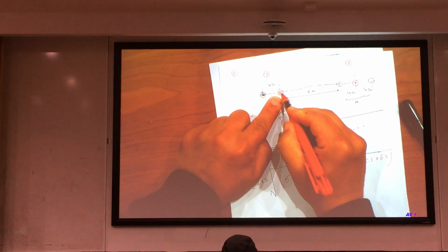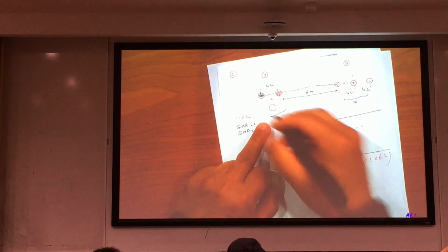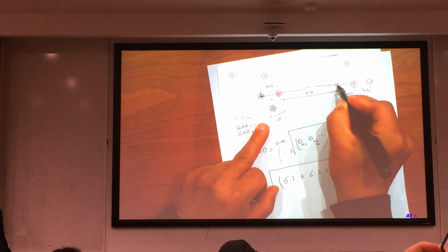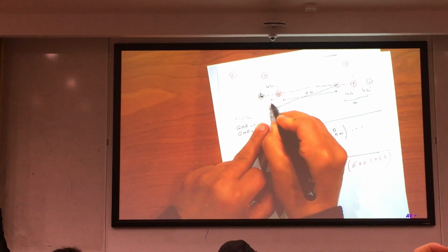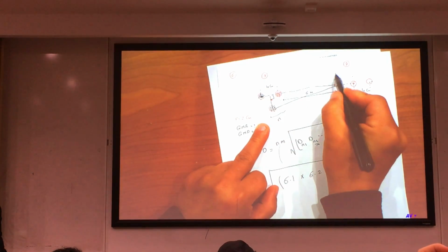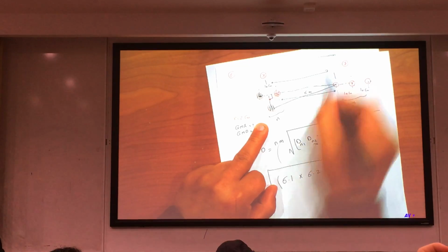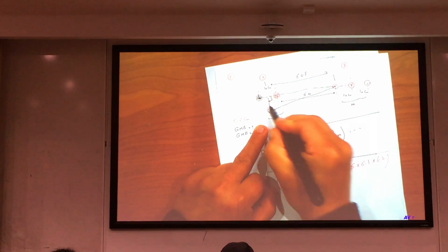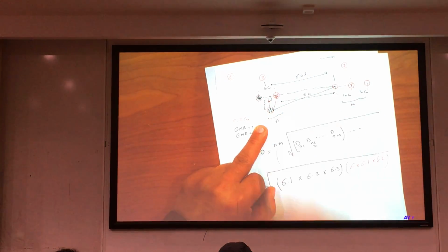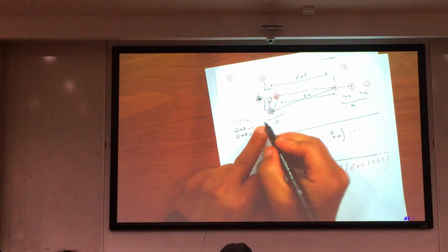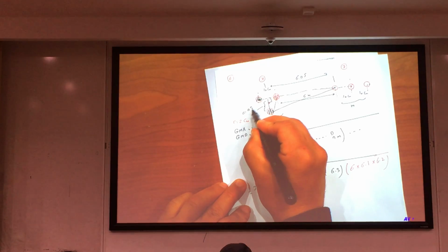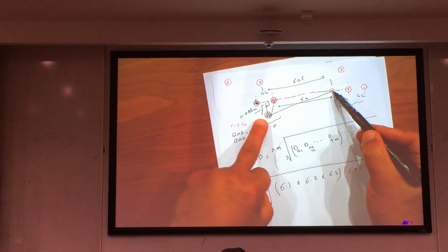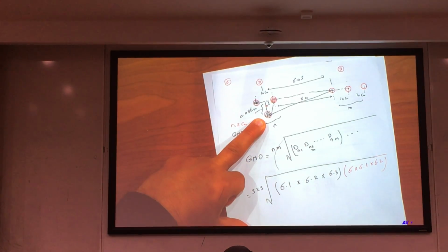You finished with this conductor, take the third one, which is this one. And this might be a little bit complicated because you have to calculate it from triangles. So this distance, first, can be calculated from this triangle, which has a distance here. This one is 6 meter and 0.05 meter, half of 10. So 6.05. And this distance is calculated from this small triangle here. I calculated it and it's like 0.086 meter. Then you can calculate this distance. So this distance will be almost 6.05.